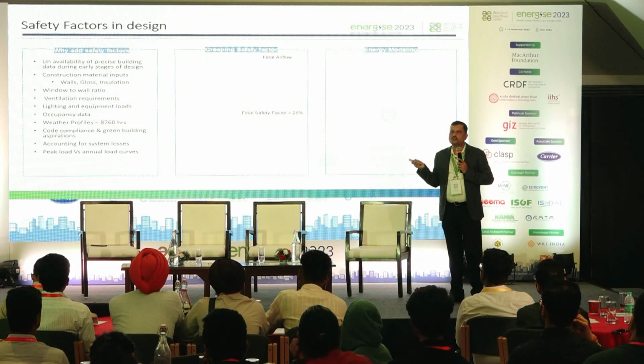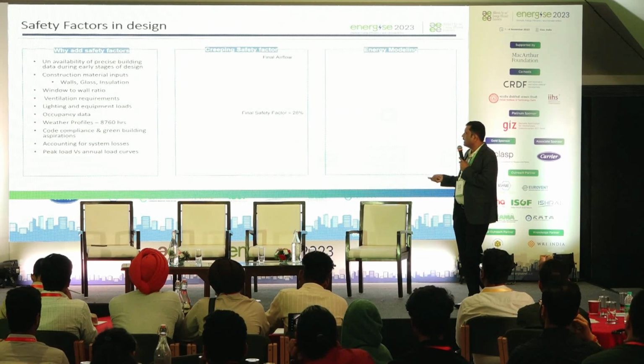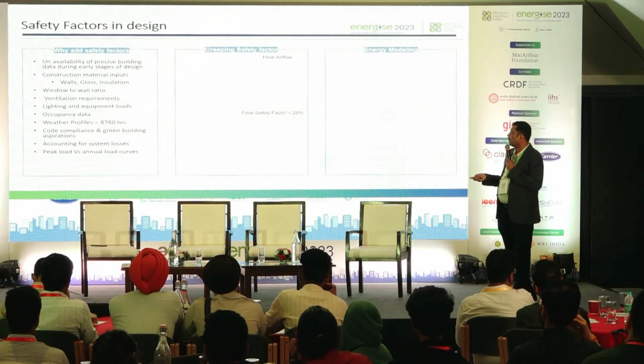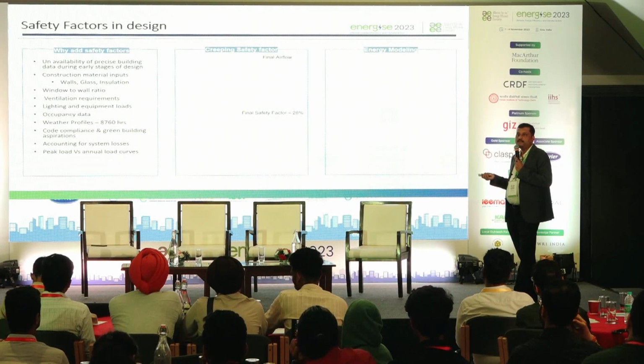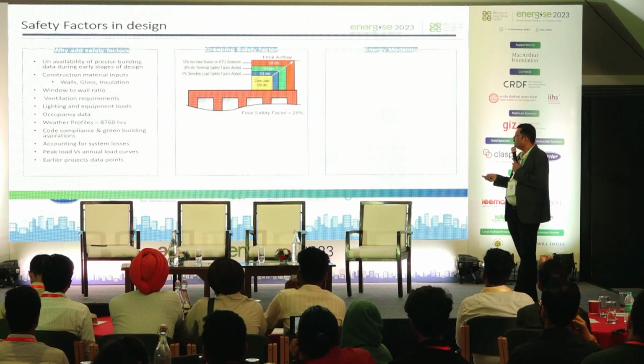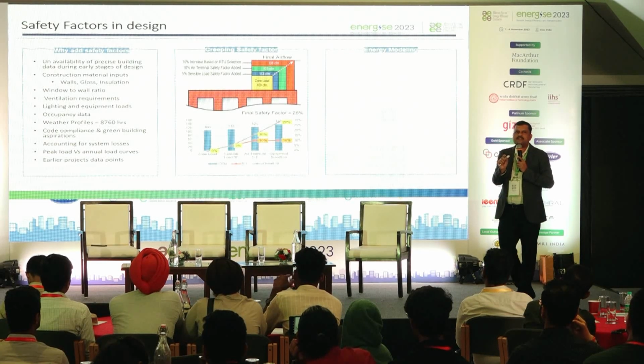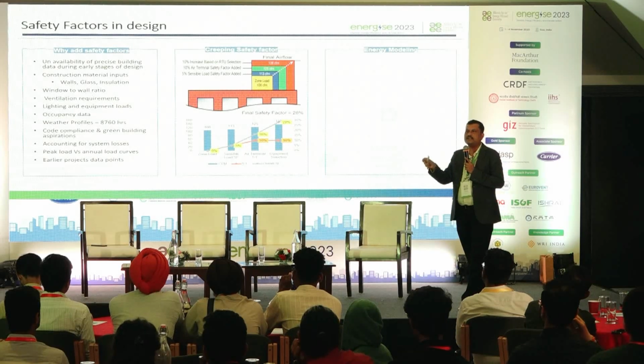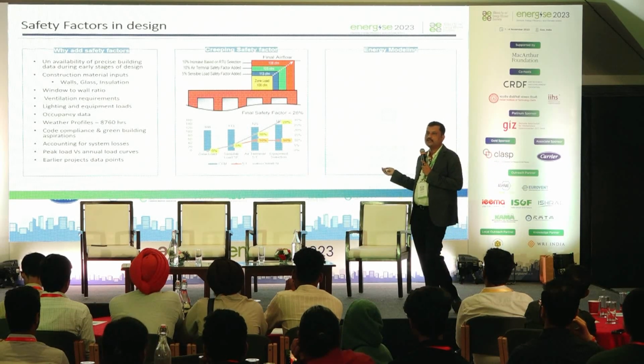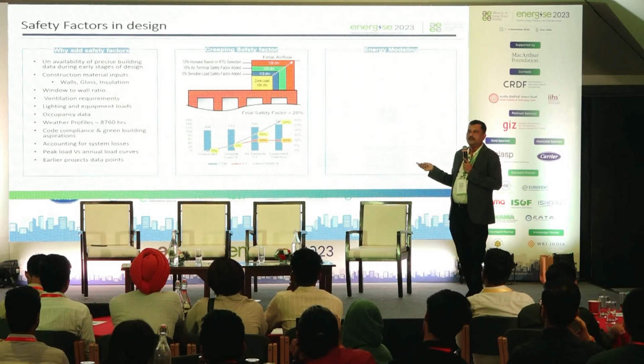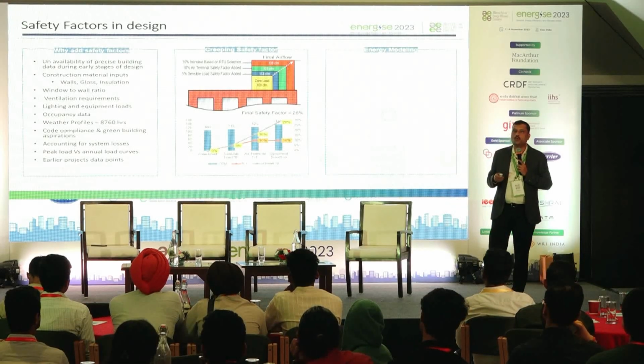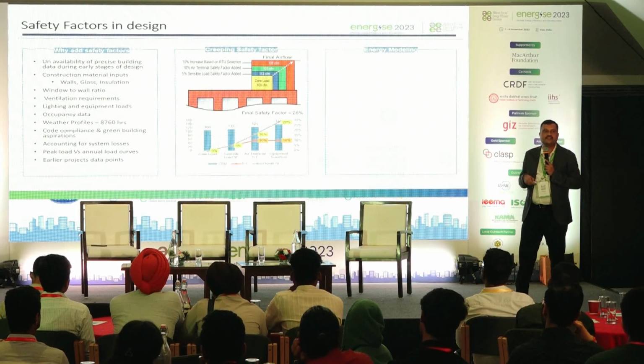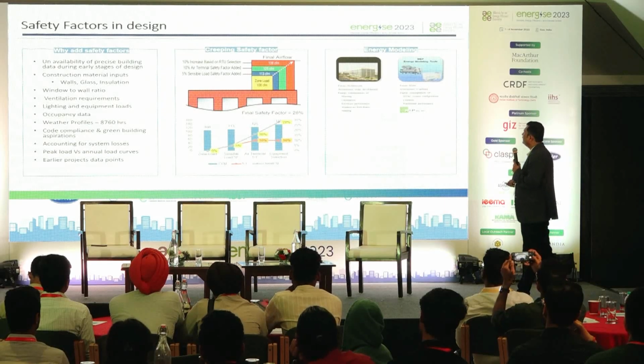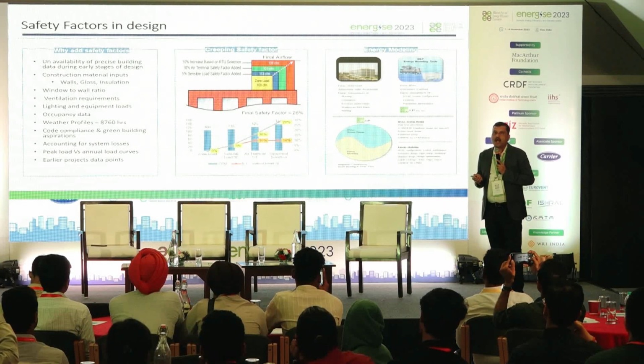Your window to wall ratio may or may not be clear, your lighting area, occupancy data—all these factors add to the safety factors. When we notice it, adding just 5% here and another 5% there can result into something like 28%. What are we doing? We are basically oversizing at every level, at every step.